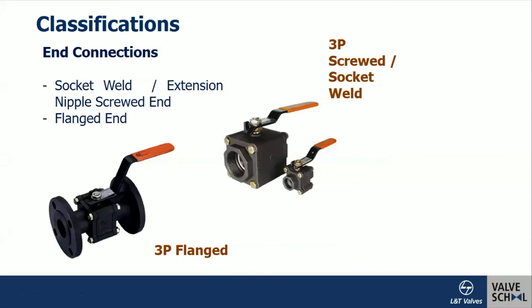We can also classify ball valves based on end connections. The popular one is flanged end connection, where flanges couple with pipeline flanges. Small-bore valves have socket weld and screwed end connections. Floating ball valve sizes start from 1/4 inch (DN8) up to DN200 (8 inch), with some manufacturers making 10 inch as well. Socket weld end connections are also available with extension nipples so that contractors need not disturb the internals during welding.